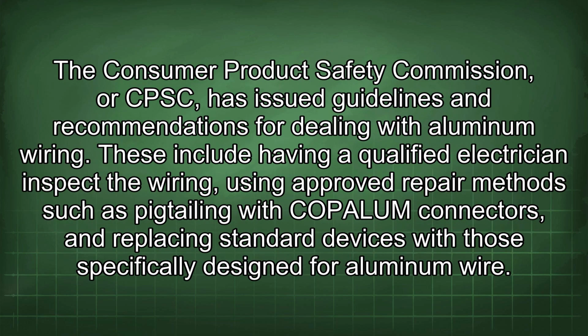The Consumer Product Safety Commission, or CPSC, has issued guidelines and recommendations for dealing with aluminum wiring. These include having a qualified electrician inspect the wiring, using approved repair methods such as pigtailing with COPALUM connectors, and replacing standard devices with those specifically designed for aluminum wire.